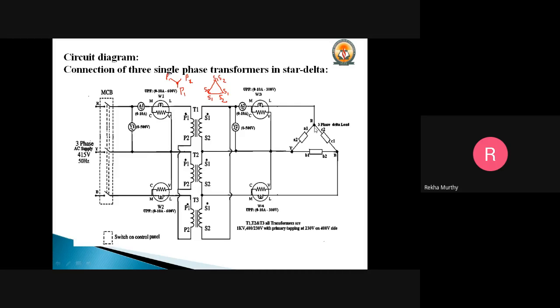And respectively we need to connect the three phase load, resistive bank load. On the next part, where the wattmeter was existing, in the same position the wattmeter should be copied, and we need to connect it as usual with the VV connection, which connects back to S2 and S1 of the first and second transformer. The voltmeter should be inserted across the supply side and across the load side, which you have to observe.